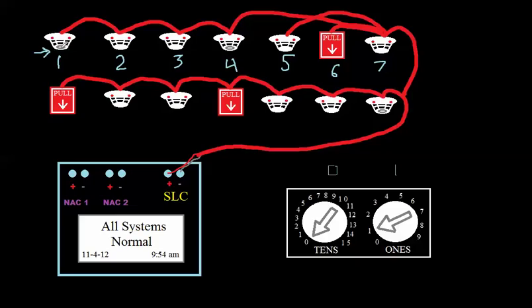Now once I pick the addresses in the field, I have to go into the panel's program and tell it, okay, device one is a heat detector. Device two is a smoke detector, and so on and so on. And the panel is going to use this data communication to always check in with it. And that's the reason that I can T-tap wherever I want, because as long as this is connected, the panel doesn't care what order it's wired in, at least, again, on a Notifier and a FireLite. As long as they're all on this loop somewhere, it's going to poll all the devices that I tell it should be there. So let's say I skipped device three. I never told it that smoke detector three existed. I told it that one, two, four, five, six, and seven all existed. It would just check for those devices.